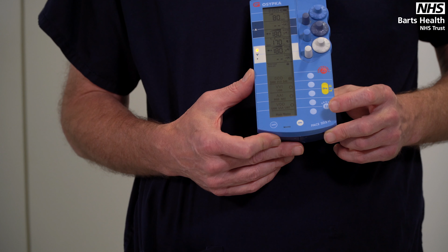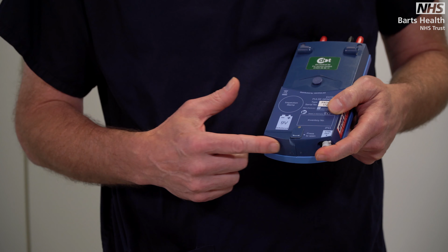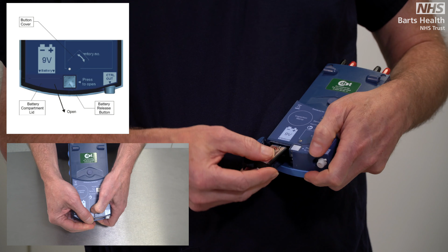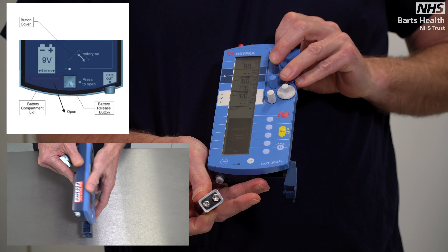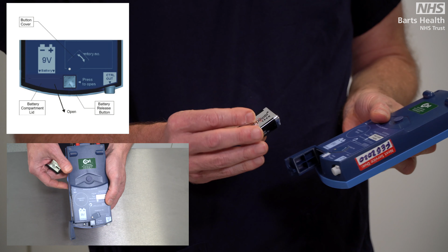Okay, in order to change the battery, you need to turn the pacemaker over. The pacemaker has a little battery compartment on the bottom of it, and you can access the control for opening that by sliding this little tab across, and you press the button, the door will open and the battery will fall out. Notice that the pacemaker carries on working even when the battery is out, and you have about 30 seconds to put a new battery back in. It doesn't actually matter which way round you put the battery in, but just make sure that you've taken the wrapping off it before you reinsert it and close the base of the pacemaker. So that is really very straightforward. The important thing though is to notice that the battery needs changing.